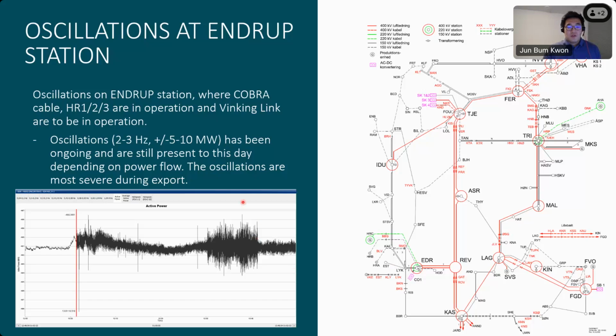Some oscillation issues recently happened in this area, at what we call the Endrup stations. We observed oscillations around 2 to 3 hertz, and the oscillation magnitude depended on the power flow. We were able to observe around 5 to 10 megawatt plus-minus oscillations. That happens from time to time, meaning that depending on the operation of different power electronics devices like wind power plants and other devices, we will observe these oscillations periodically.